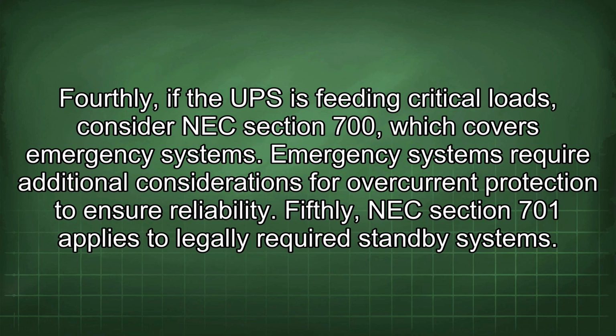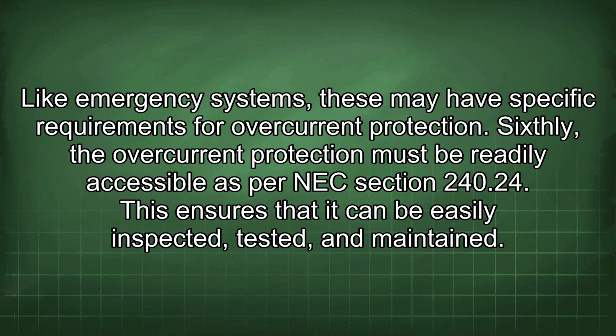Fourthly, if the UPS is feeding critical loads, consider NEC Section 700, which covers emergency systems. Emergency systems require additional considerations for overcurrent protection to ensure reliability. Fifthly, NEC Section 701 applies to legally required standby systems. Like emergency systems, these may have specific requirements for overcurrent protection. Sixthly, the overcurrent protection must be readily accessible as per NEC Section 240.24. This ensures that it can be easily inspected, tested, and maintained.